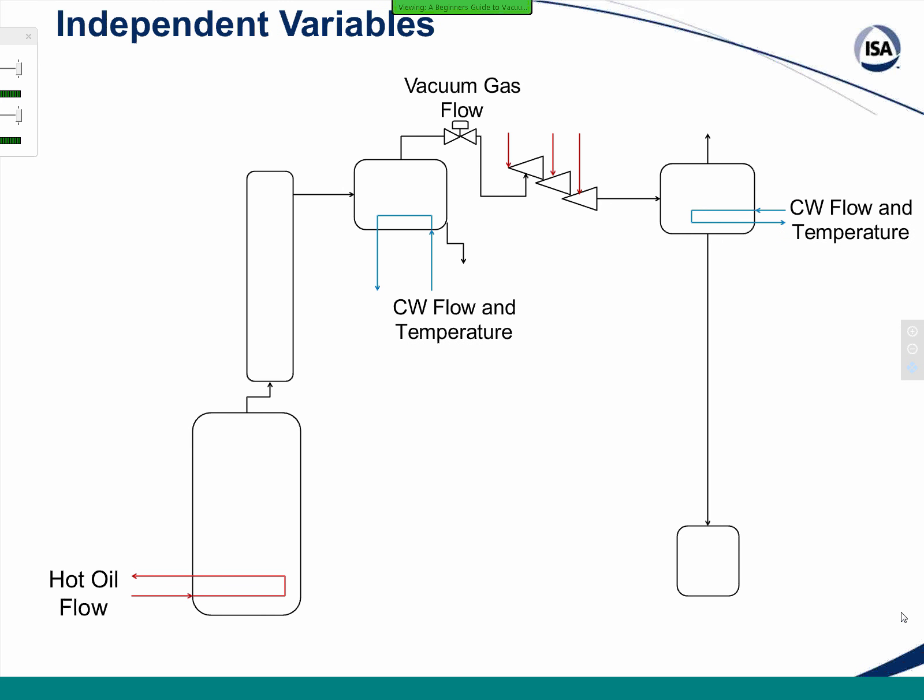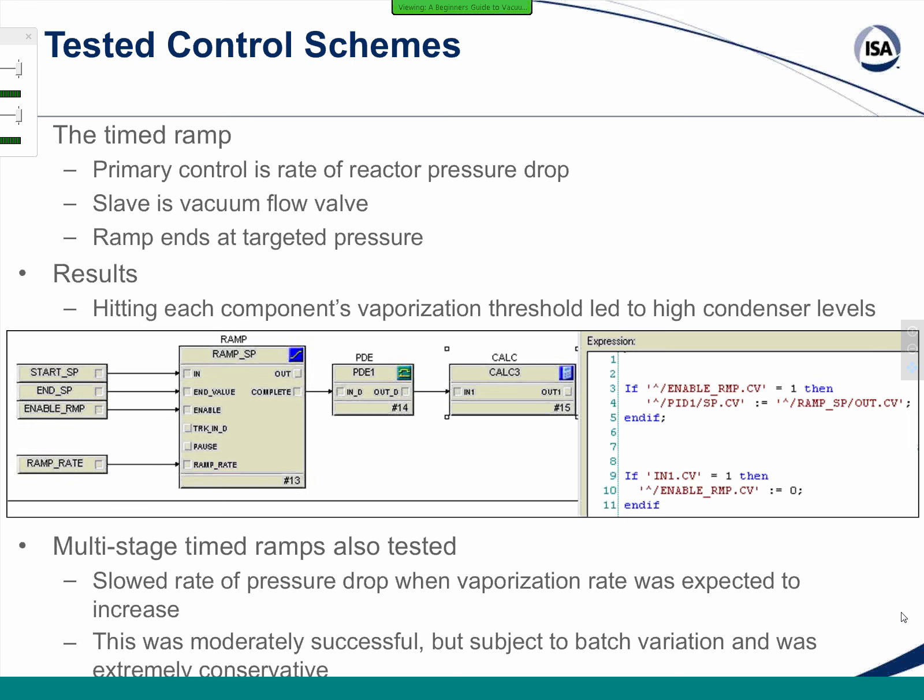Now let's look at what we have available in order to control those variables. We can turn the following knobs: we have hot oil flow, which we can use to change the temperature and push us back further on that vaporization curve for the temperature and pressure. We have cooling water flow and cooling water temperature, both of which are controllable. And then the main knob is still the amount of vacuum flow that's going to the vacuum system.